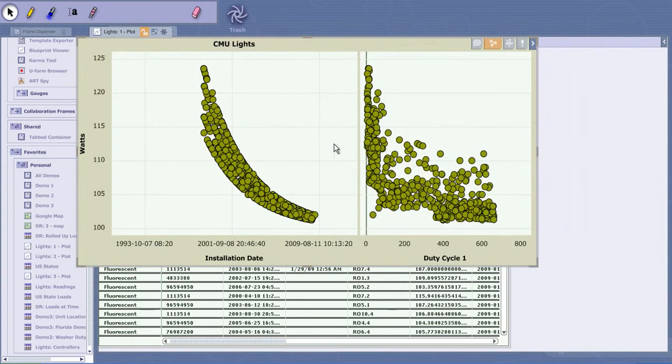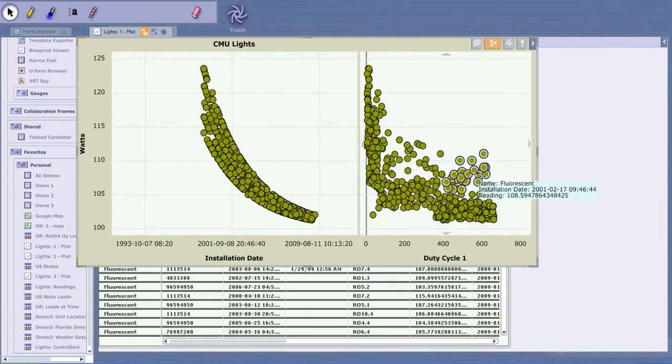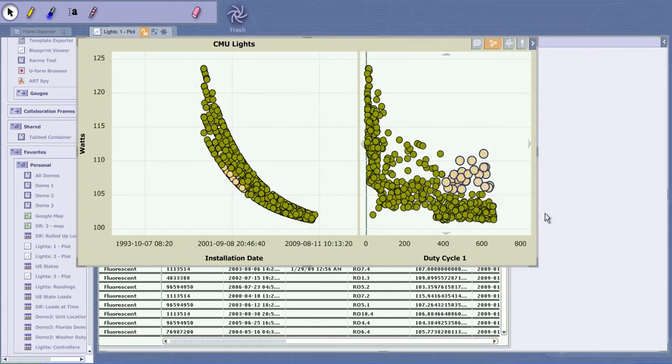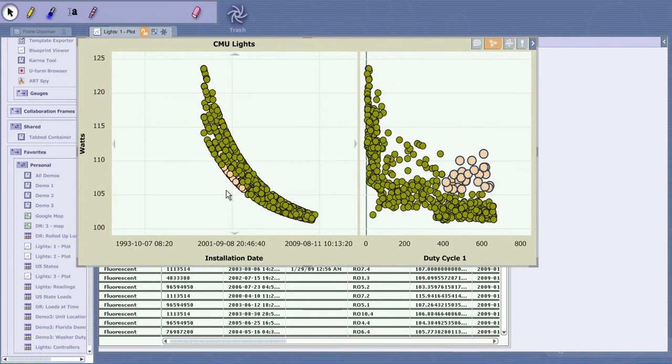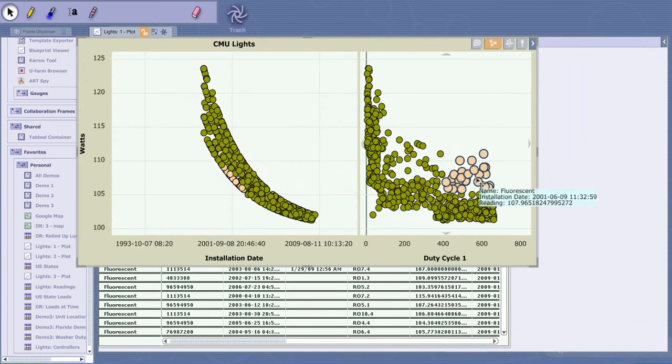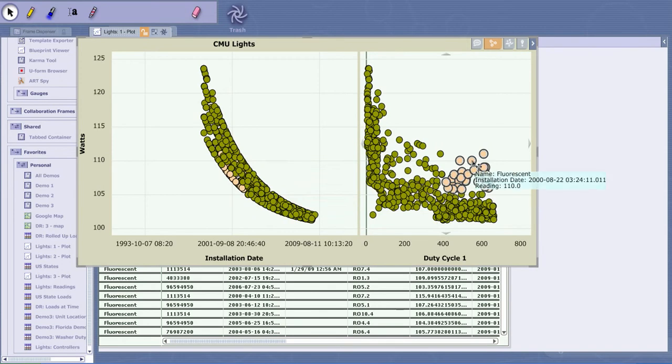Now are there some things going on here? There are some outliers - these guys not turned on and off very much, that's duty cycle, but they're still using some higher wattage. Let's color those. There's a little bit of a pattern there. Clearly stuff installed a long time ago is less efficient no matter how often you turn them on and off, and that's a function of how compact fluorescents work.